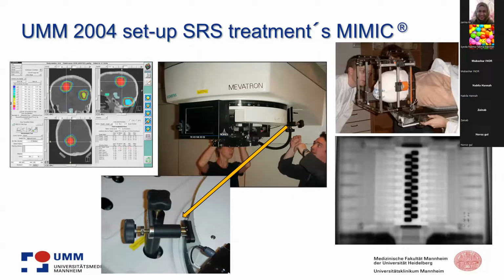During the commissioning, you see what we have learned at that time. MLCs were basically constructed for shaping irregular fields. At the beginning of the Mevatron KD2, they were not intended to deliver intensity modulated beams. So in that case, a main issue was the calibration of this mechanically calibrated MLC. And you see this, what we have done on a regular basis before every patient when we treat the patient QA plan. We have to check the modulation and the calibration, and you see here the bad calibration, and you see here the good calibration.